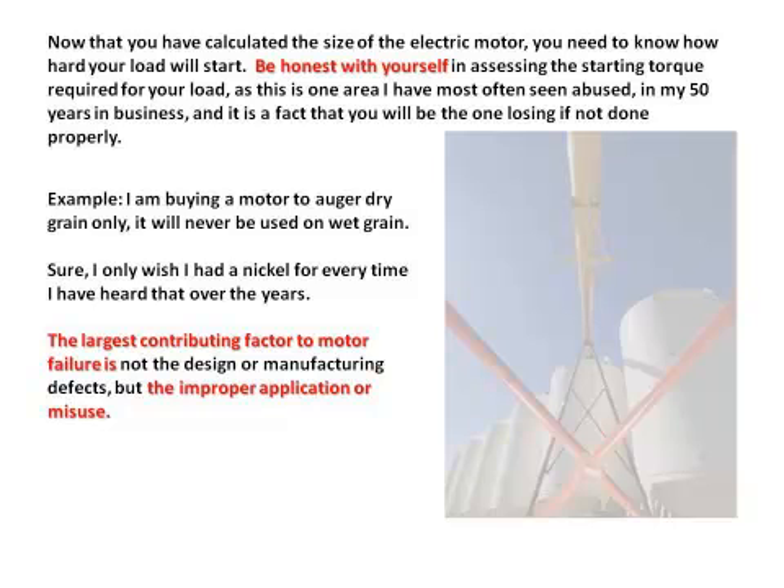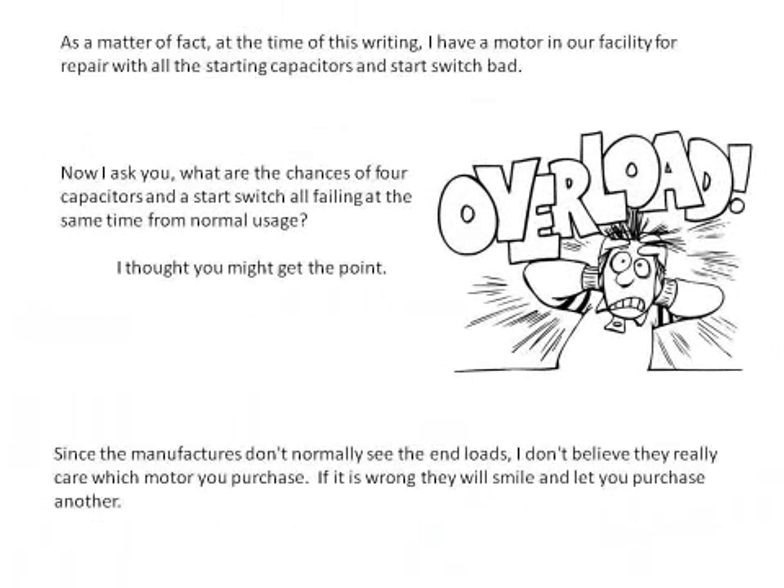The largest contributing factor to motor failure is not the design of the manufacturer or defects, but improper application or misuse. As a matter of fact, at the time of this writing, I have a motor in our facility for repair with all of the starting capacitors and a start switch bad. What are the chances of four capacitors and a start switch all failing at the same time from normal usage? I thought you might get the point.